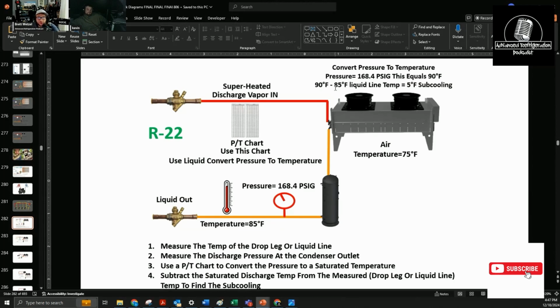No. And then unless, okay. So wintertime. Okay. So anything above 75 degrees, we should get that 3 to 5 degrees of subcooling. Anything lower than that on the ambient, because now the condenser is uber big, that subcooling is going to go exponentially, just ridiculously high.